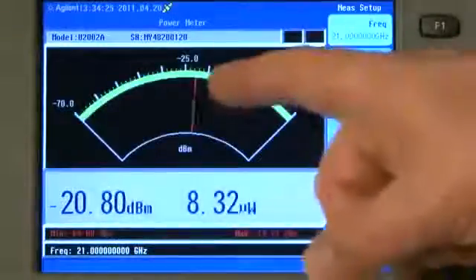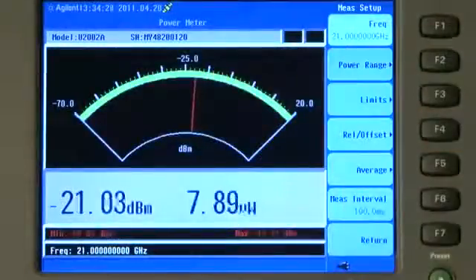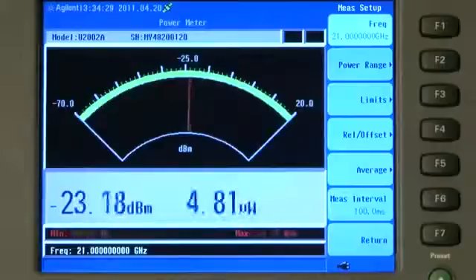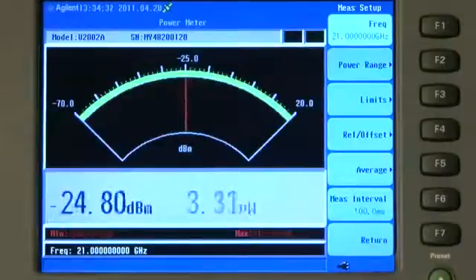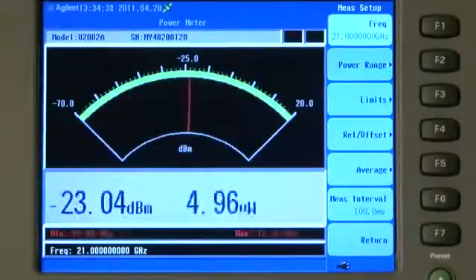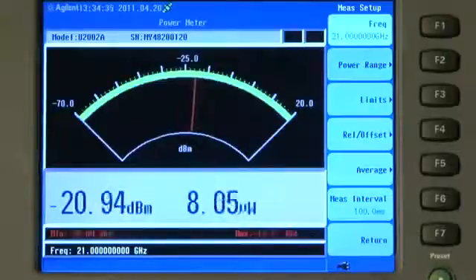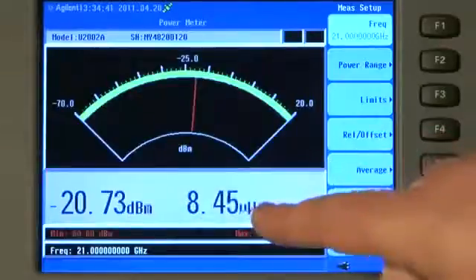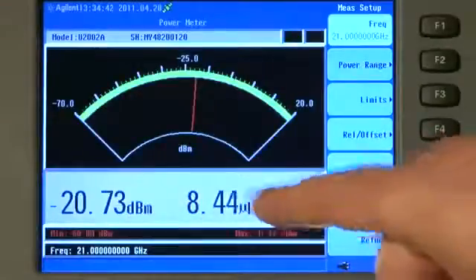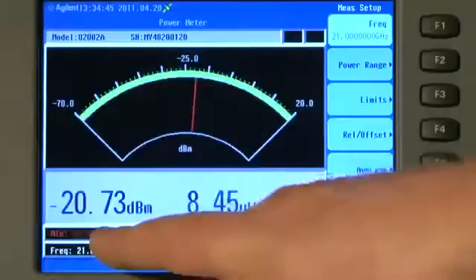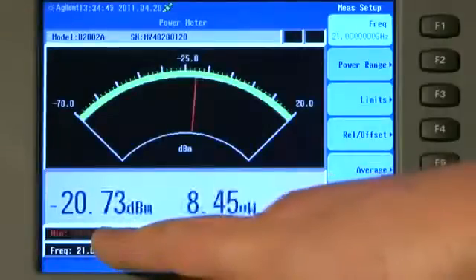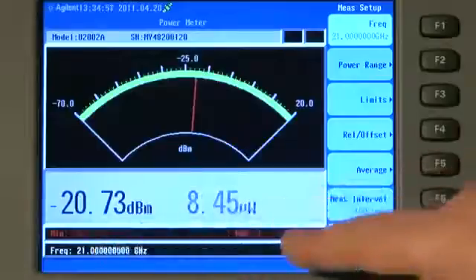Now as well as the graphical display here with the meter, you'll see as the level goes up and down such as in the situation of microwave fading, we can see the level decreasing and increasing. It shows the measured value in dBm and also in watts, in this case 8 microwatts. It also shows the minimum value or minimum amplitude that the unit has seen since we started making the measurement and also the maximum. Again, very useful if we're trying to characterize path loss or fading situations.